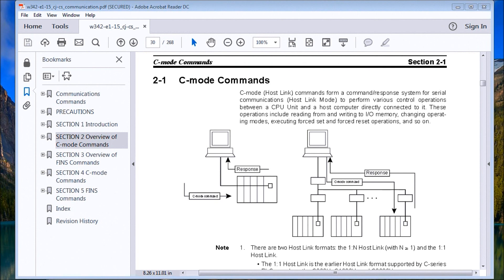Hi everyone, today we're going to be implementing the Omron HostLink protocol using Visual Basic .NET. On screen you'll see an overview of what we call C mode commands or HostLink commands. We have a one-to-one setup — one computer to one controller — and a one-to-N setup — one computer to several controllers. HostLink protocol allows you to talk serially through COM ports to up to 32 devices by assigning each a HostLink unit number.